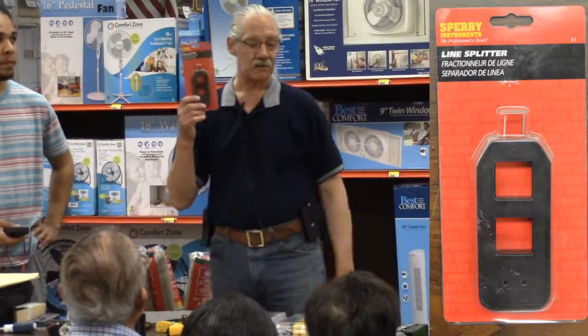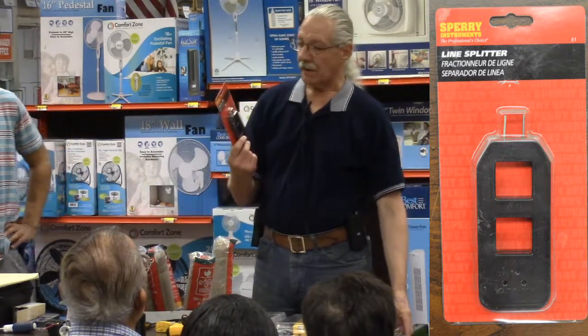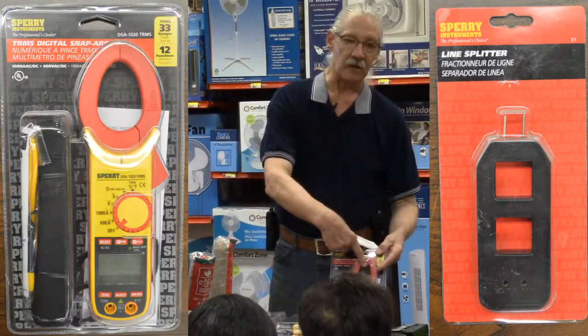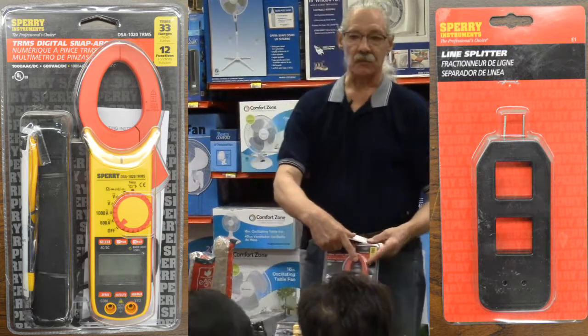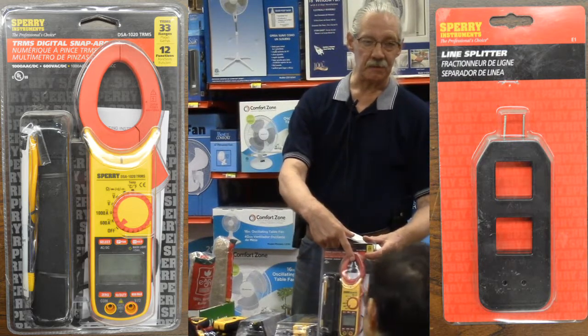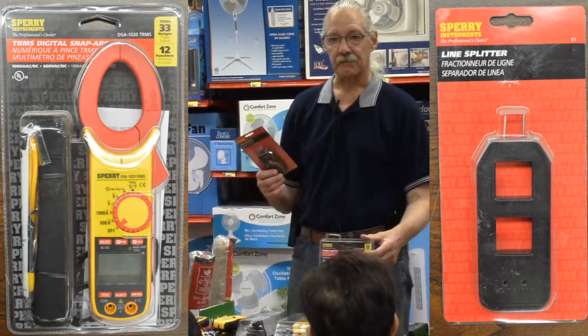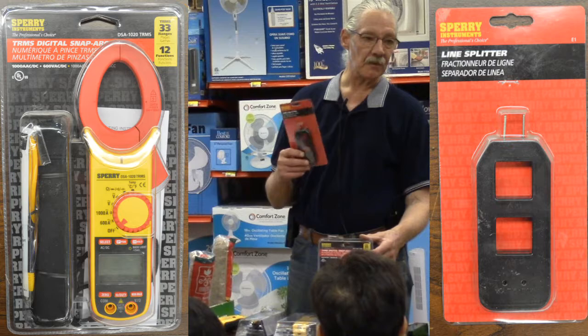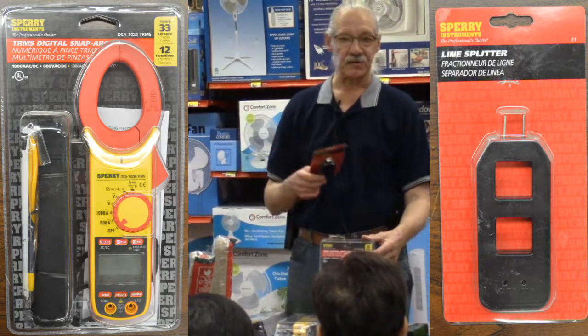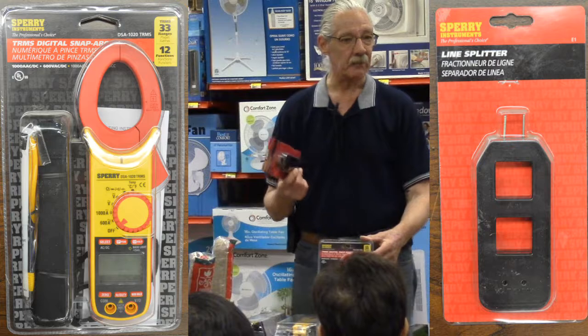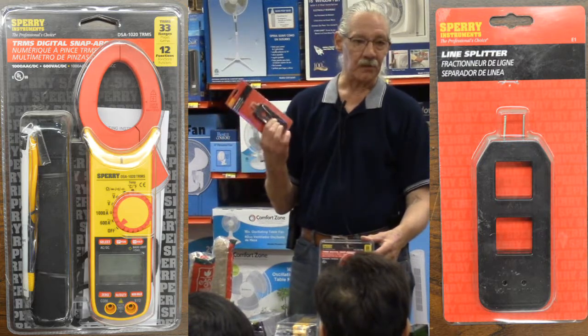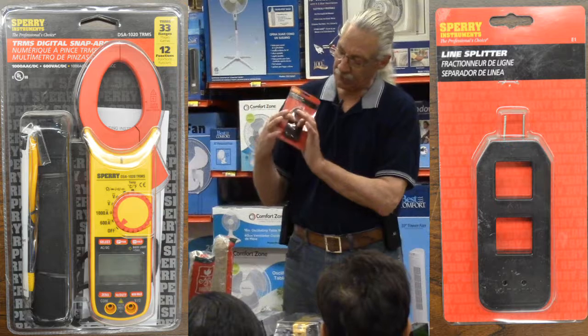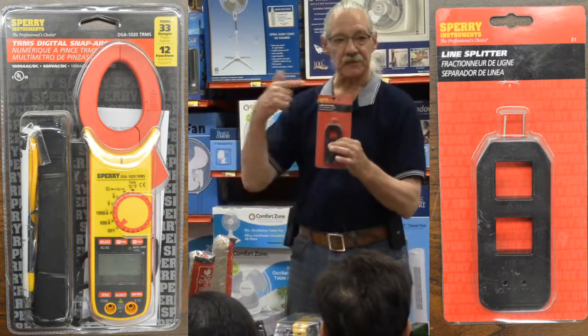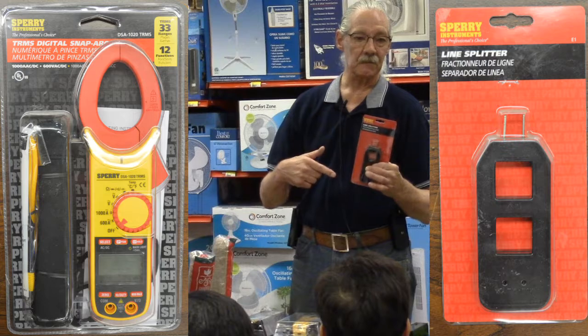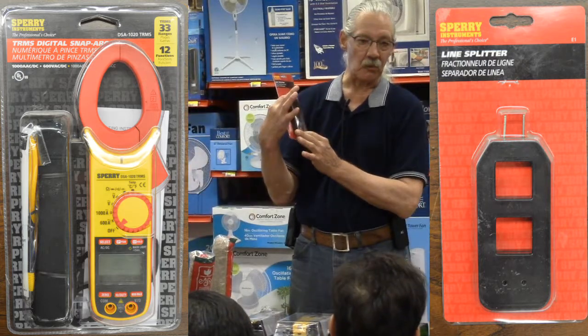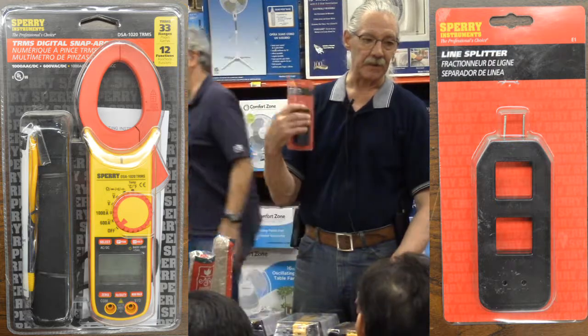This is actually an accessory to a clamp meter, where normally the clamp is just put around the one hot wire you're testing on the circuit. But if I had something that plugs in, like a big motor or a humidifier, and wanted to know how many amps it's drawing, I could plug this into the wall, plug the unit into that, and then clamp around this. That gives me the reading of whatever I plugged in, because this separates your hot and neutral wiring, so you can get a reading with the clamp meter.